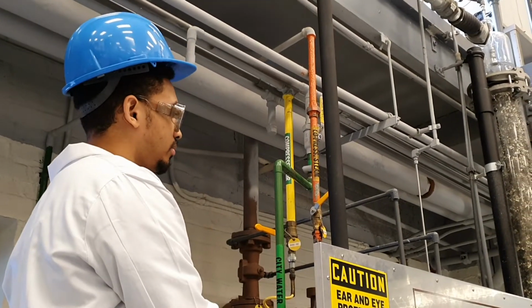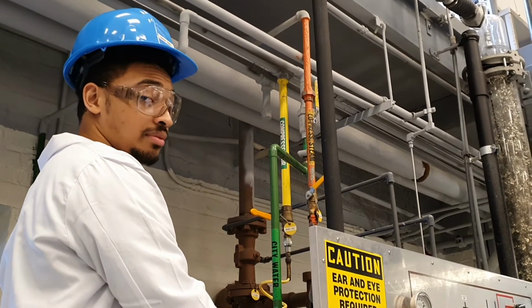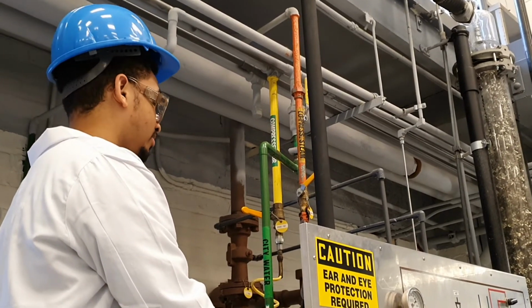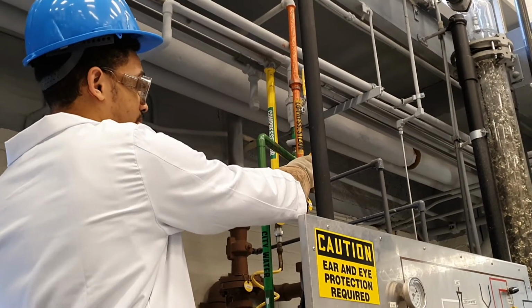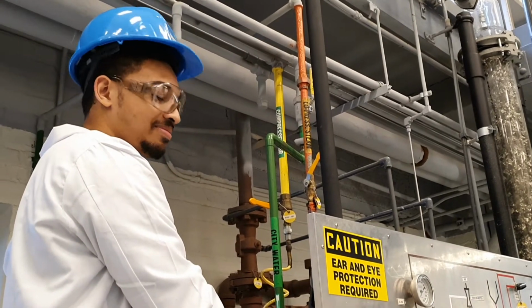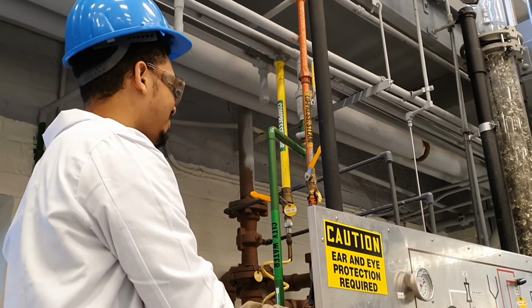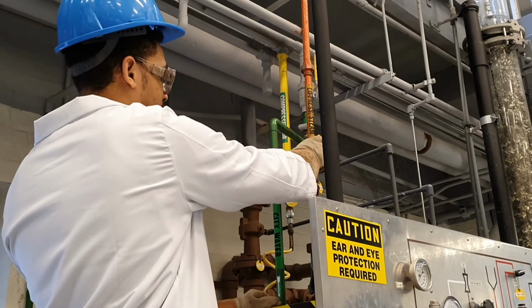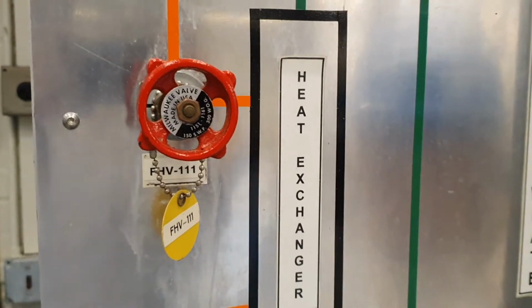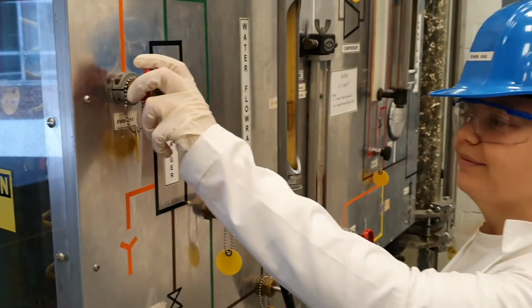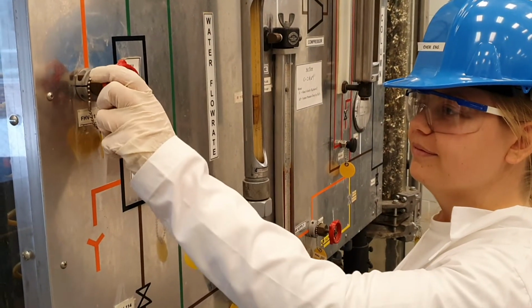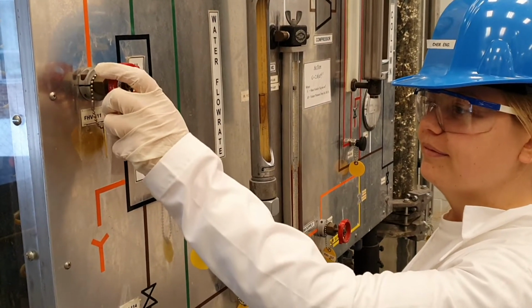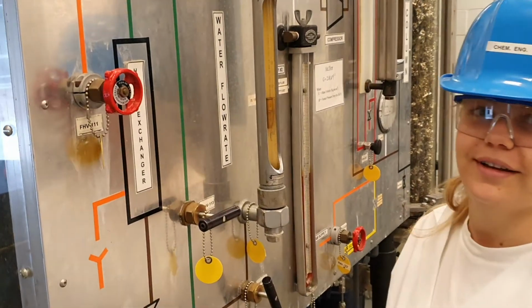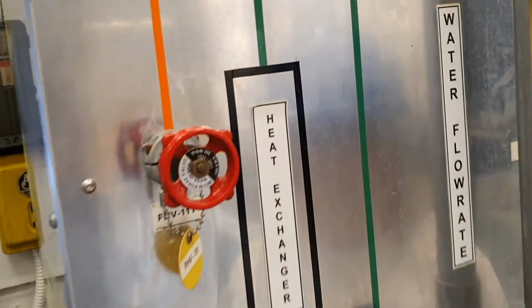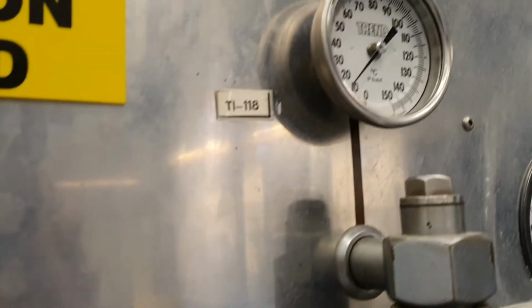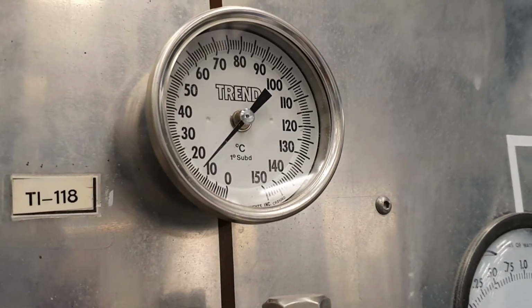When adjusting FHV 116, heat-resistant gloves should be worn due to the high pressure and temperature conditions. A ladder will be required to reach FHV 116. Have a second group member hold the ladder as the first group member opens the steam valve. Open FHV 111 partially to allow the steam flow into heat exchanger E110. Be careful not to open this valve fully, otherwise the water entering the column will quickly rise to a temperature above 80 degrees Celsius, the operating temperature limit for this column.